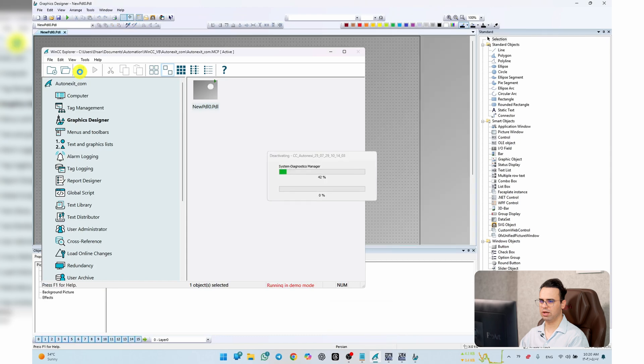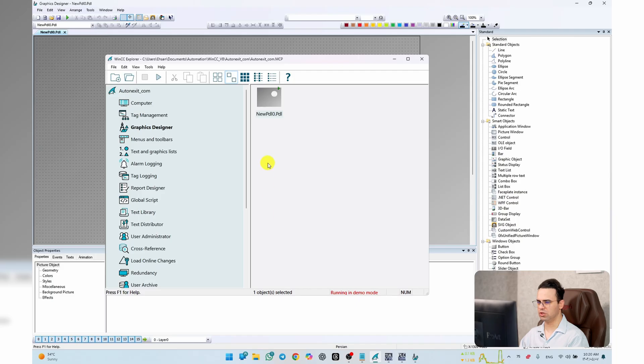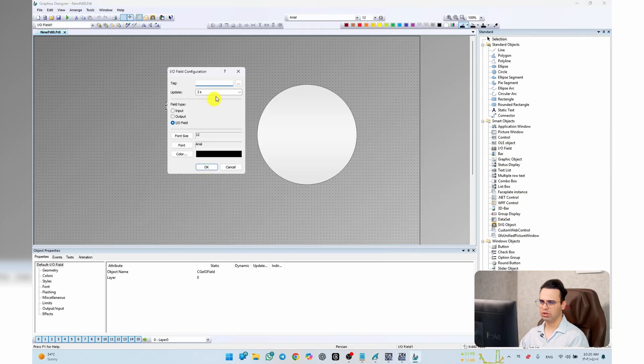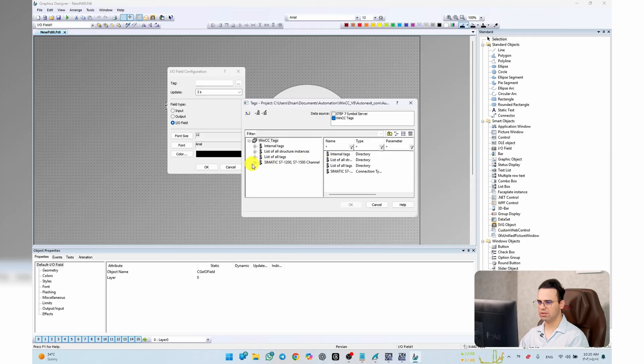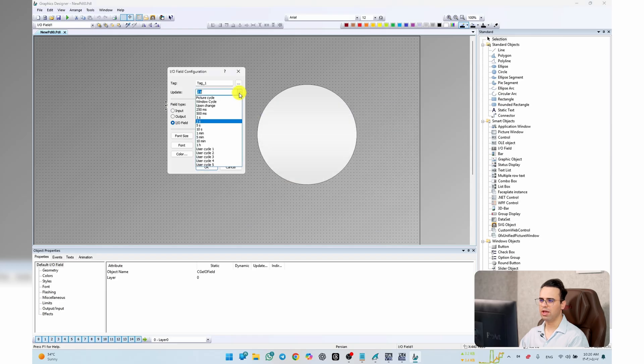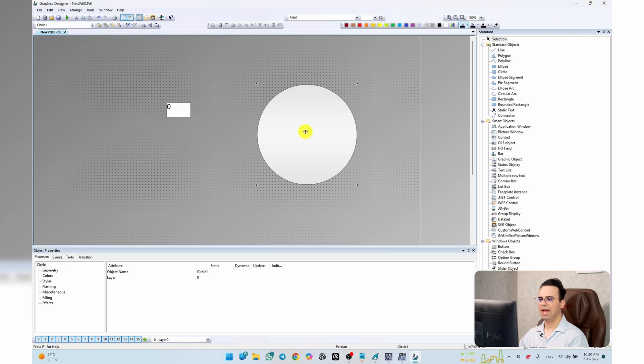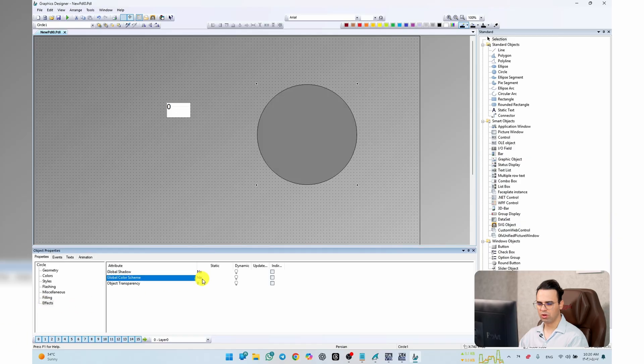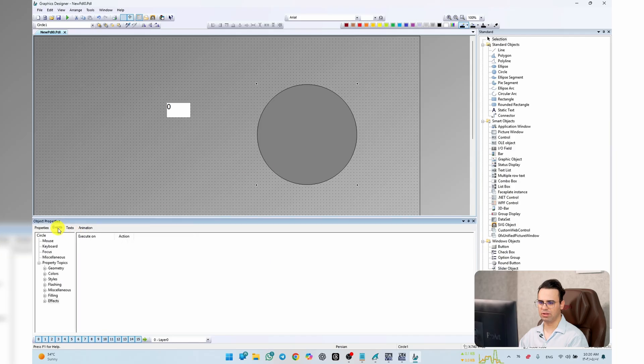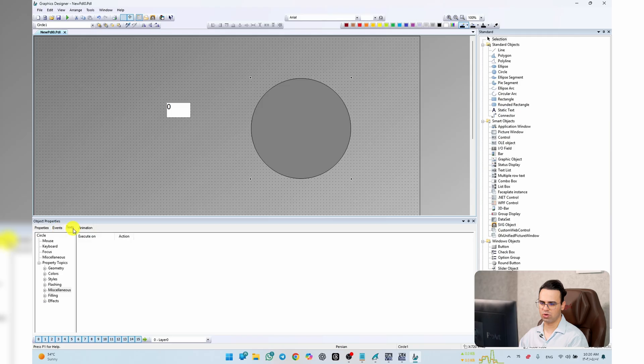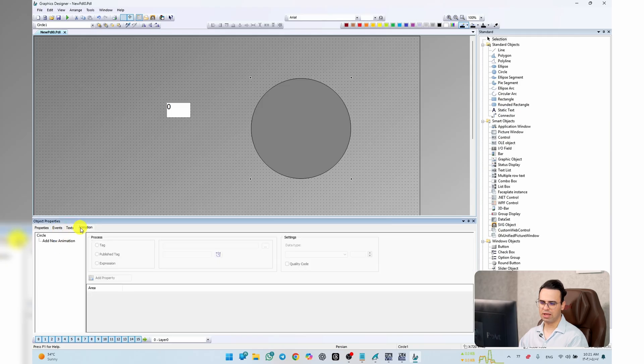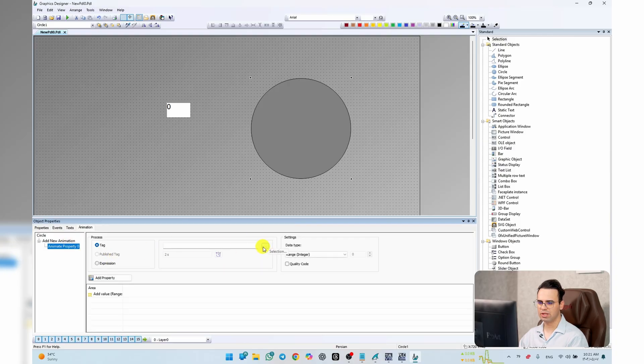Stop the project and go to Graphic Designer. Tag One is the first tag — I want to use an I/O field to change Tag One. Set the driver to OMS Connection and Tag One, hit OK, trigger on change, and set font size to 24. For Tag Two I want to use it as feedback to change the color of a visual element — use Animation.